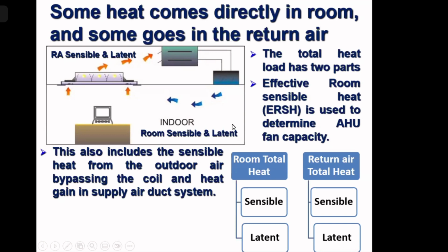You see, the supply air ducting coming from the AHU to the supply air grill, taking the blue air in the room. So that ducting also has got heat gain, and sometimes the supply air duct gain, and in addition to that, there is a fan motor. Air handling unit has got a fan. So fan motor is there. So depending upon the location of the fan motor, we'll discuss in the next slide. Depending upon the location of the fan motor, air handling unit fan motor, we have to add heat of that fan motor either in the return air side or in the room sensible.